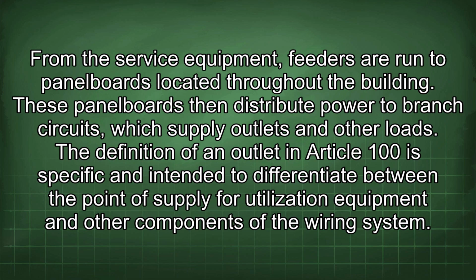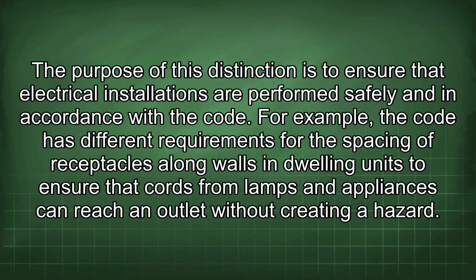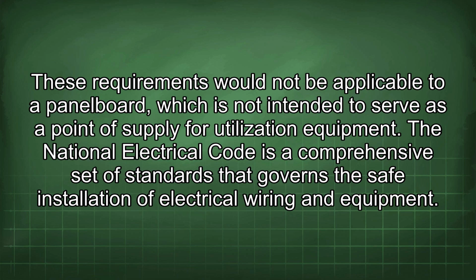The definition of an outlet in Article 100 is specific and intended to differentiate between the point of supply for utilization equipment and other components of the wiring system. The purpose of this distinction is to ensure that electrical installations are performed safely and in accordance with the code. For example, the code has different requirements for the spacing of receptacles along walls in dwelling units to ensure that cords from lamps and appliances can reach an outlet without creating a hazard.